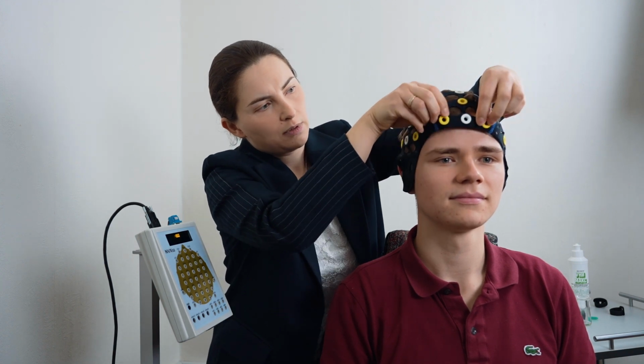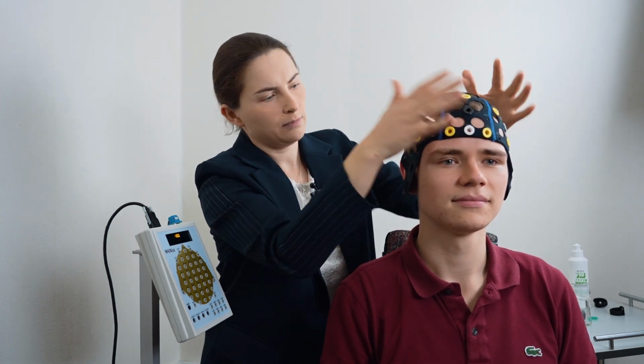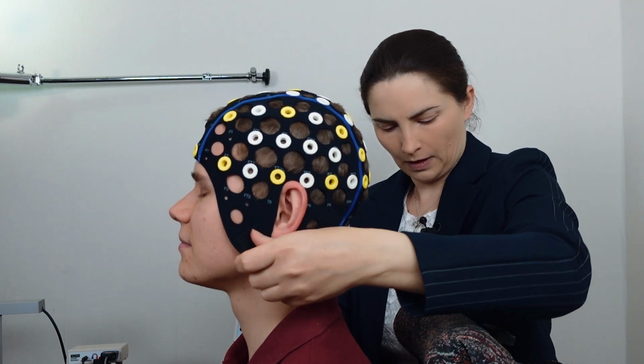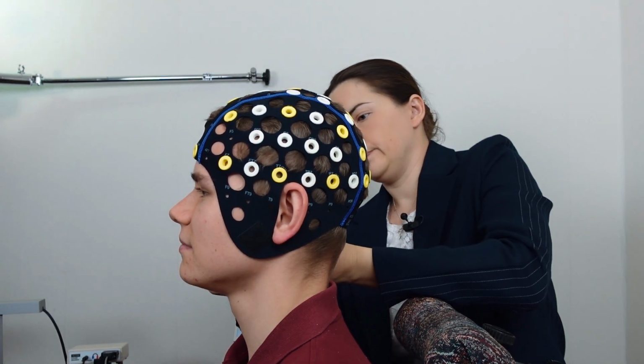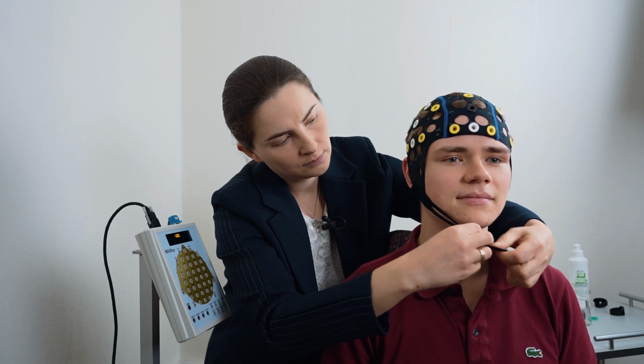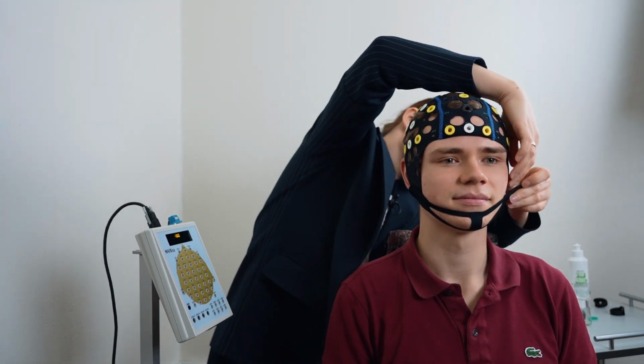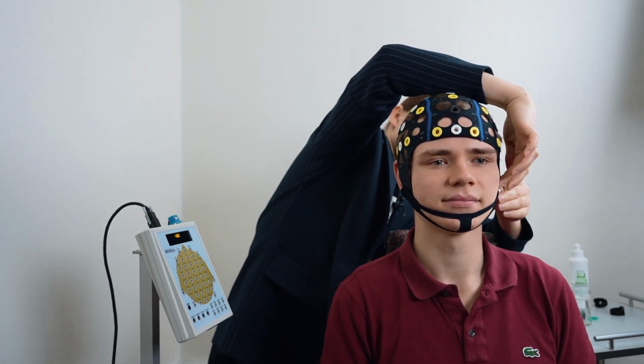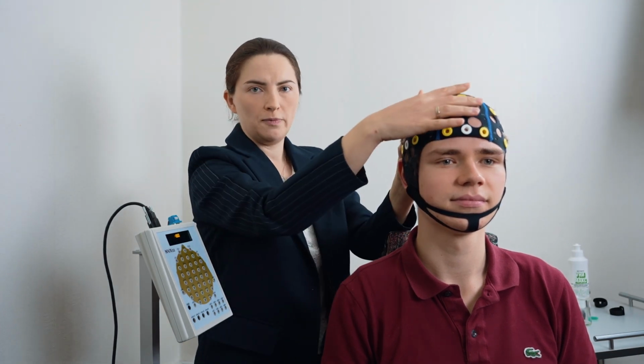Place the helmet on the head of the study's participant. Fix it. We should pay attention to where the locking rings will be located. They should be exactly above the branches that we will install according to the previously discussed plan. Now, let's move directly to the installation of the electrodes themselves.